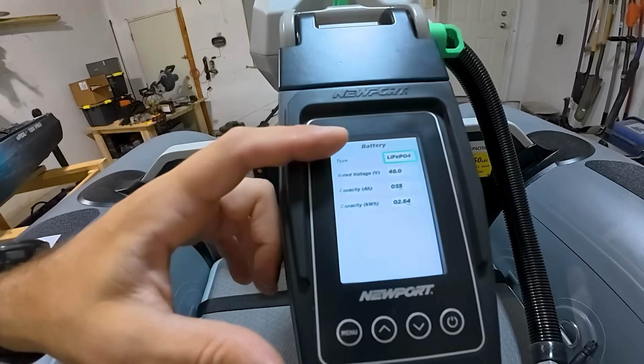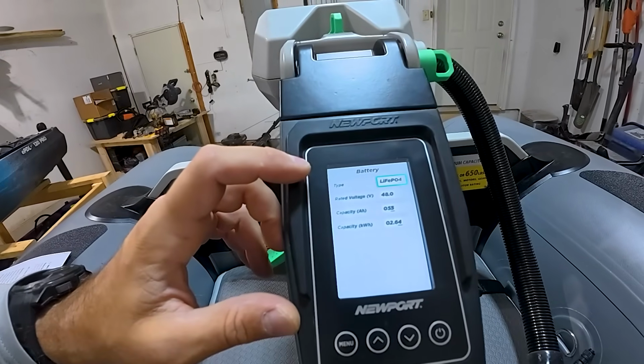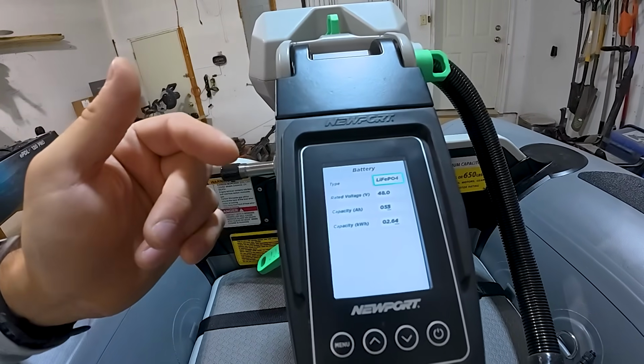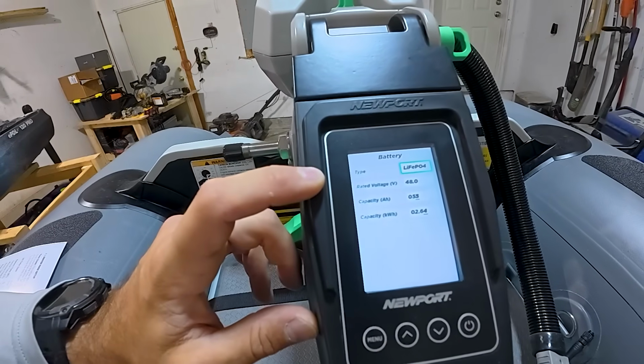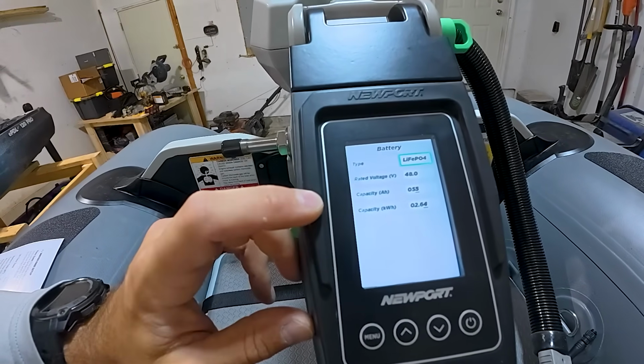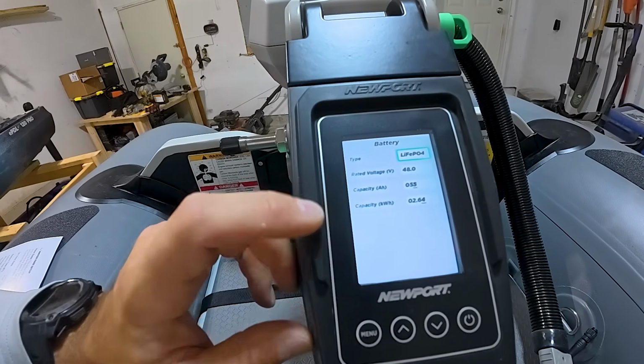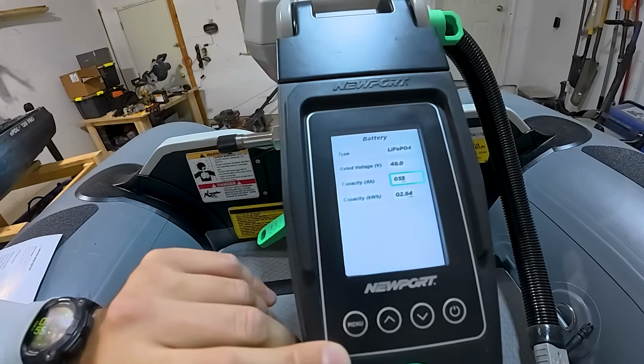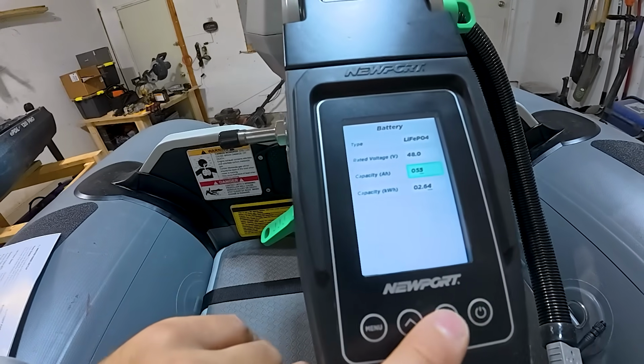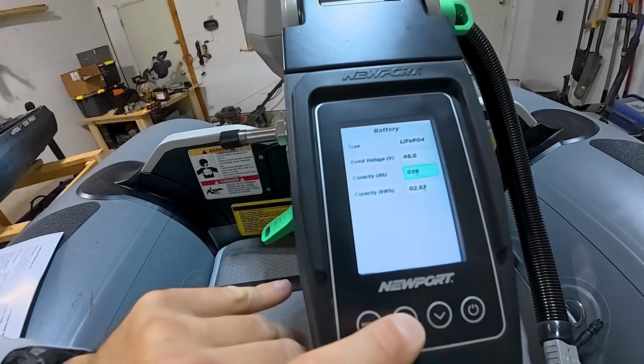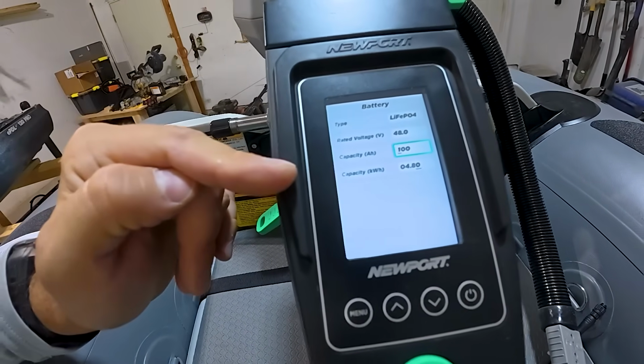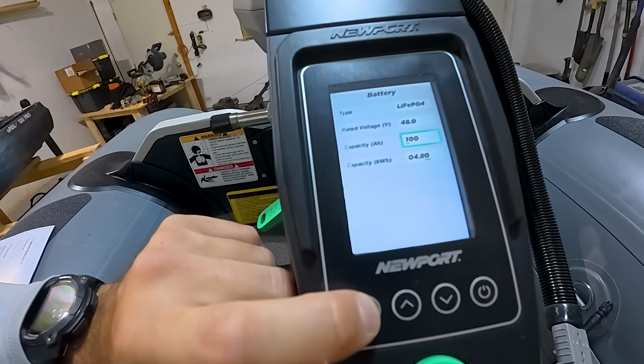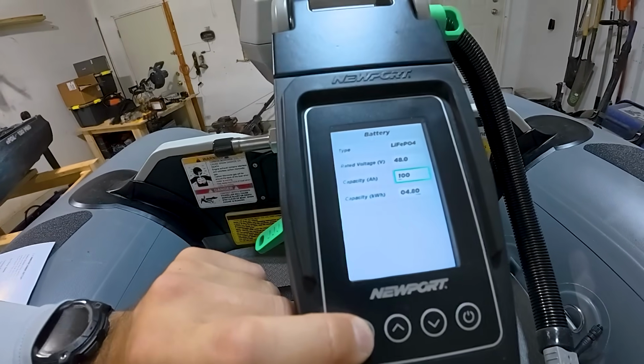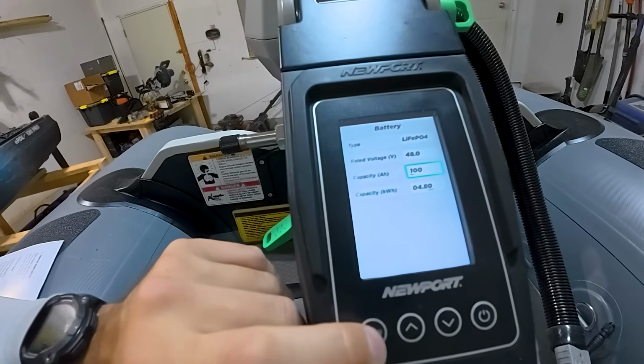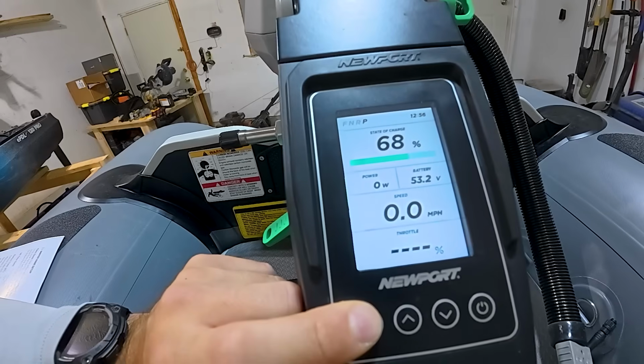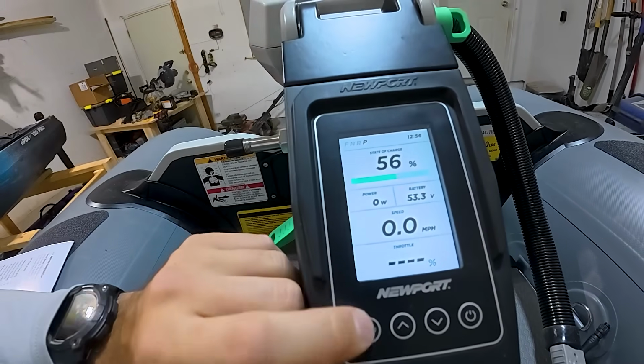Then you go to the battery, it auto selects the type of battery you're running, but if you see an error here, you can adjust it. You've got the rated voltage on your battery, so we've got 48 volt. Capacity in amp hours, this one's saying 53, so that is incorrect. We're going to go down here, hit power to enter that, and we're going to up that to, boom, 48 volt, 100 amp hour, done. It's the only battery I have for this, so that's what we're going with. Then we're going to cycle through to exit out of the menu, boom. So that's pretty cool.